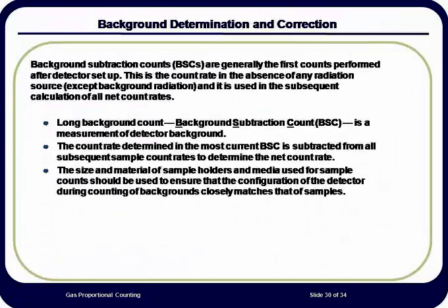Although shorter count times may lead to larger uncertainty, they also provide for better sample throughput. Thus, routine checks of both long and short background counts should be performed. Longer background checks are generally performed at a lower frequency than the background count times that match the sample count times. When the count times for the samples and the background are the same, they are called paired.